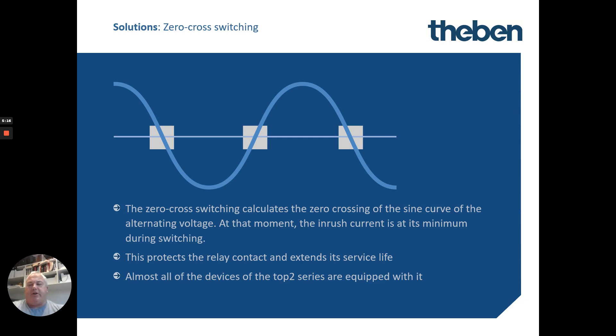Theben have a solution. The first of their ingenious solutions is zero-crossing switching. We all know electrical is transmitted in a sine wave, alternating between positive and negative. The point where it switches over — the zero point — is where there is the least potential. They've made smart electronic devices with the ability to pinpoint when the load is crossing over the zero point and make the switching at that time, which can save a lot of potential damage.